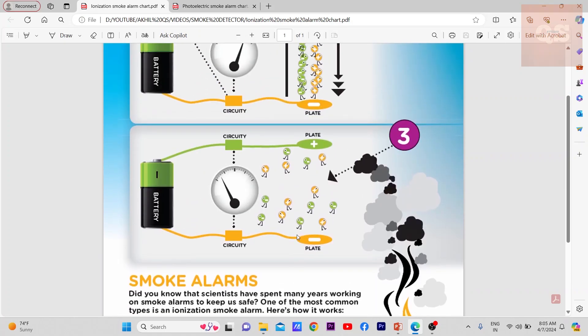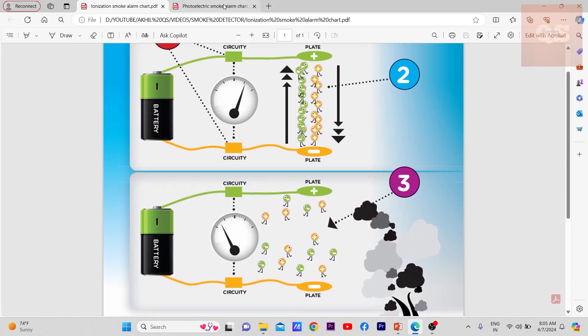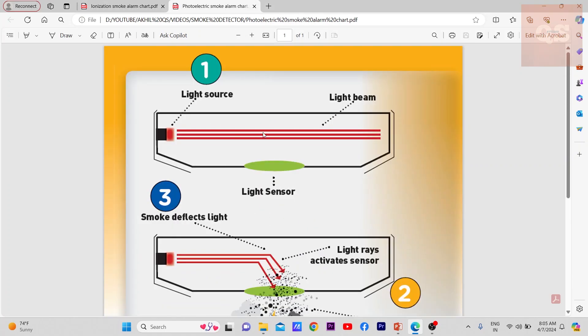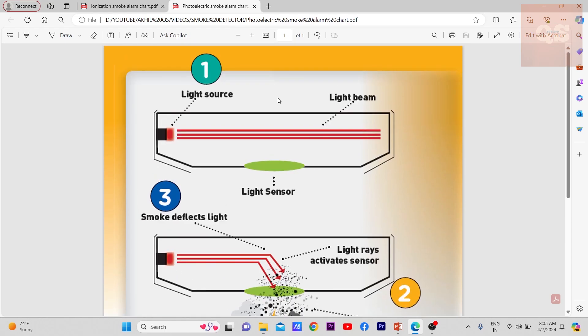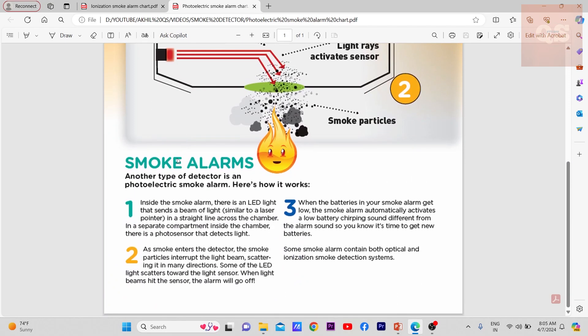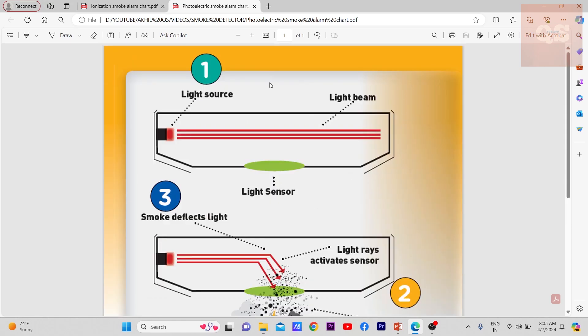Now let's look into photoelectric type. Here this is the basic diagram of a photoelectric type. Inside the smoke alarm, there is an LED light that sends a beam of light, similar to a laser pointer, in a straight line across the chamber. In a separate compartment inside the chamber, there is a photo sensor that detects light. This is the basic structure.